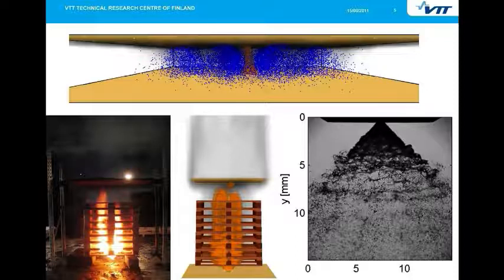It's also challenging from the physics viewpoint, because there are more suppression mechanisms in a water mist system than with conventional sprinklers. We have to deal with surface wetting, gas phase extinction, and the blocking of radiation. And also, it's not straightforward to characterize the water mist sprays in terms of the quantities that we need to specify as boundary conditions for the computation.